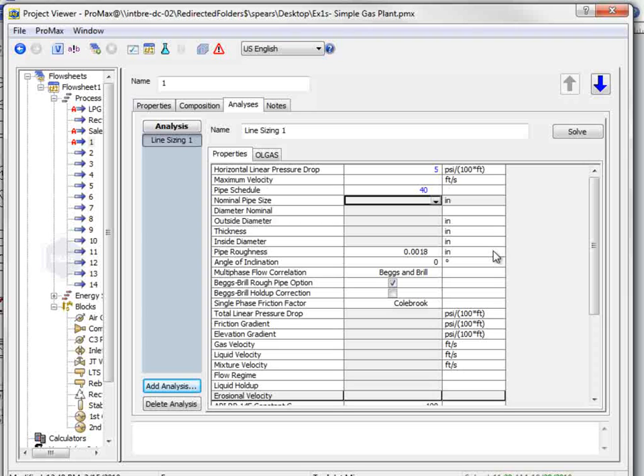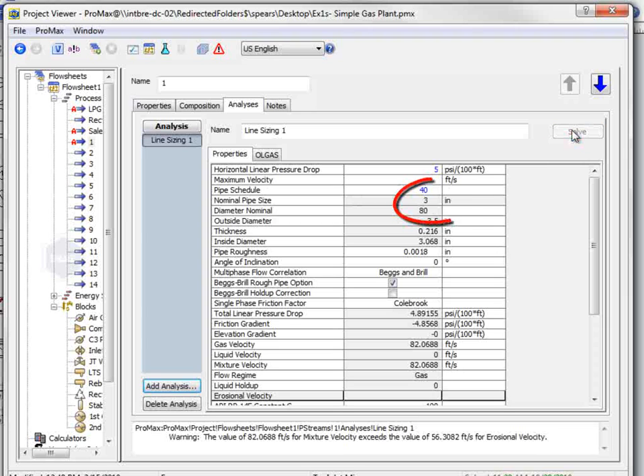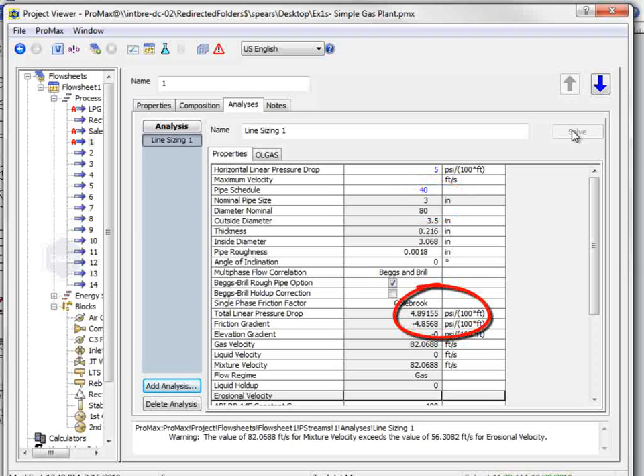This calculates that we need a 3-inch pipe. The pressure drop is actually 4.89 pounds per 100 feet, and the velocity is 82 feet per second.